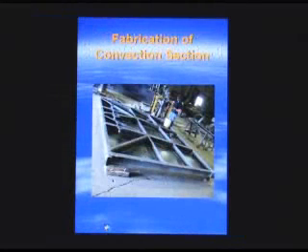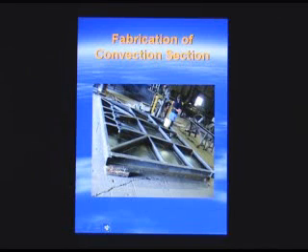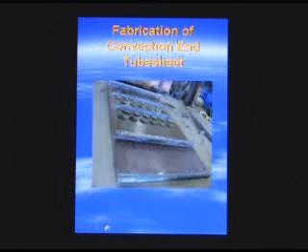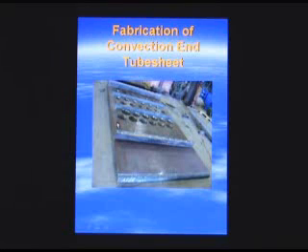A heater going down the road. This is one of the sections of the convection section. This is the tube plate. Tubes will basically be running back and forth, and you'll have a U-bend here where the tube comes out of this plate, turns around, and goes back into the section.